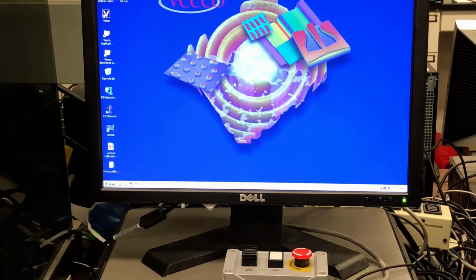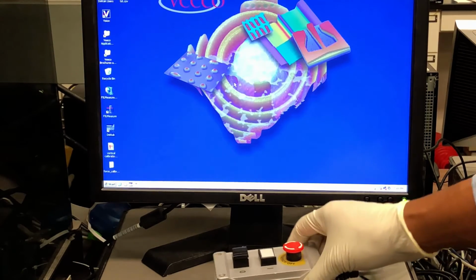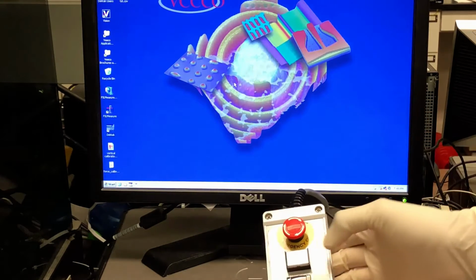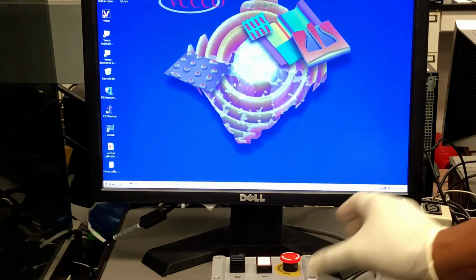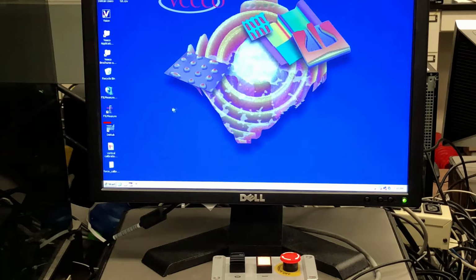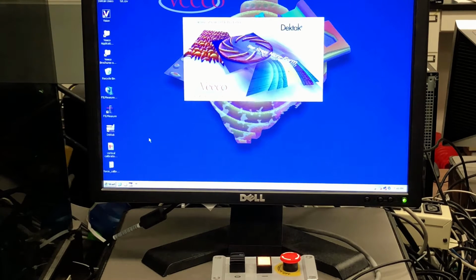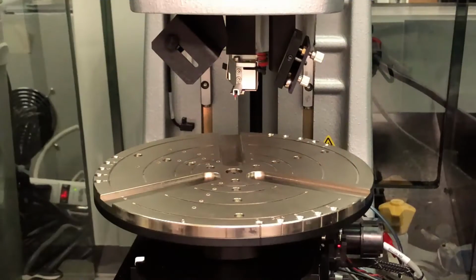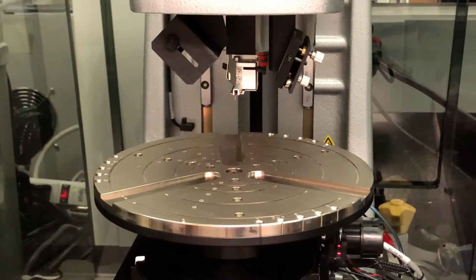When you're ready to load the software, you may notice that the sample stage needs to be turned on. Just grab the remote control in front of the screen and press on to power it up. Then locate the Dektak icon on the screen to open up the software. We'll have to be patient while the software loads, as there are a few adjustments that should be made to the sample stage.